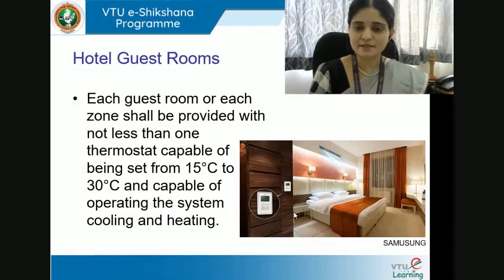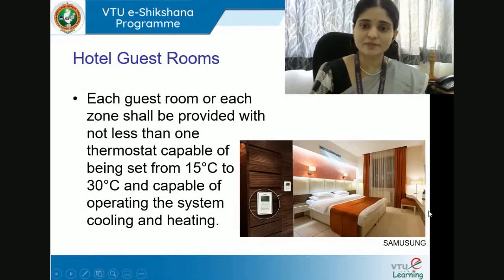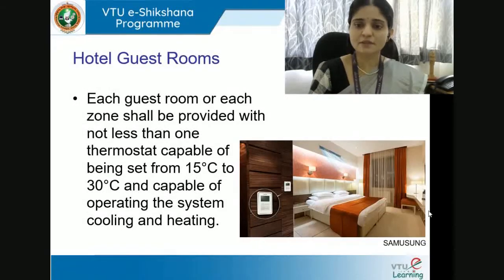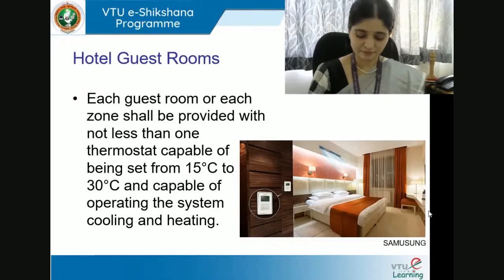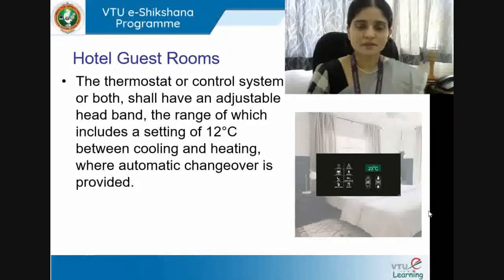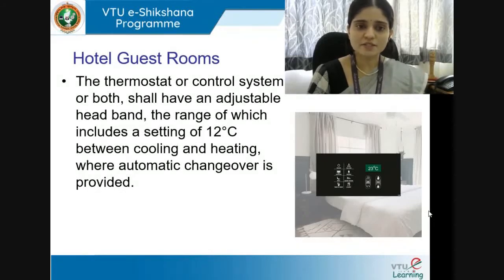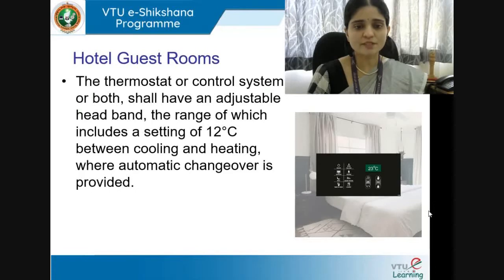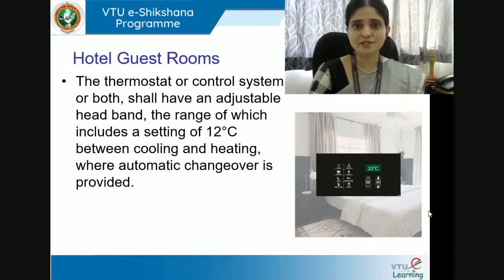The user interface is typically at about 1200mm from the floor level. The thermostat or control system shall have an adjustable deadband, the range of which includes a setting of 12°C between cooling and heating where automatic changeover is provided. Setting the system for automatic sensing via the thermostat and self-adaptation is advisable.